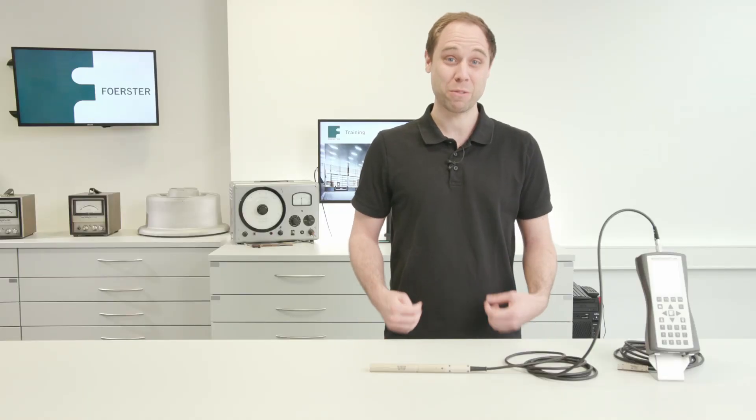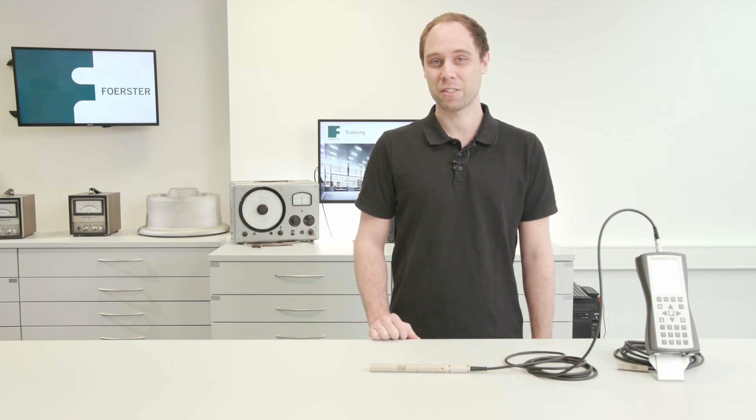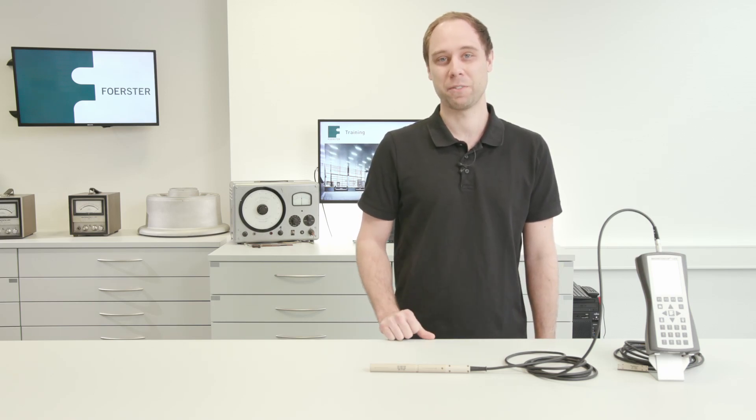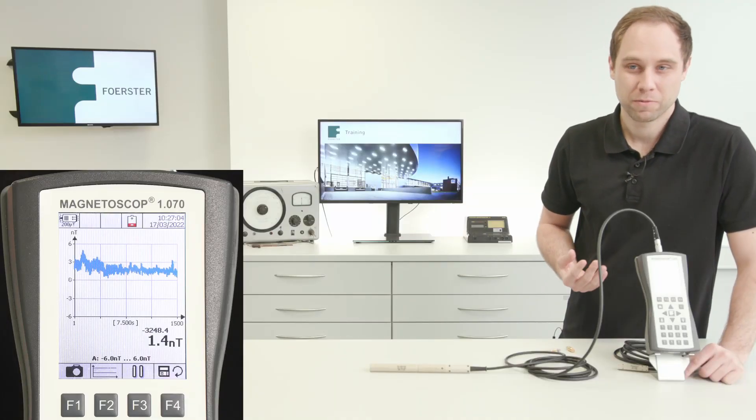Now we have our stable measurement setup with a differential probe, so we can start to measure very small magnetic fields. Components like these are used in MRI systems. For components in MRI systems, it's very important that they don't have any residual magnetic field.